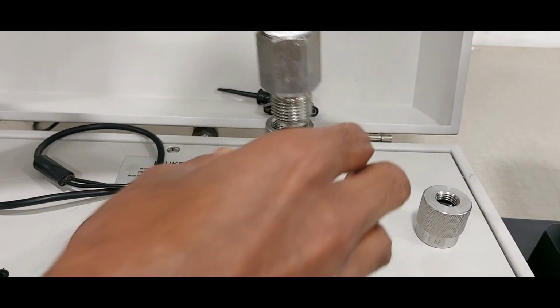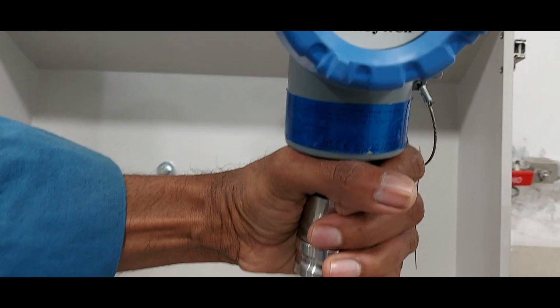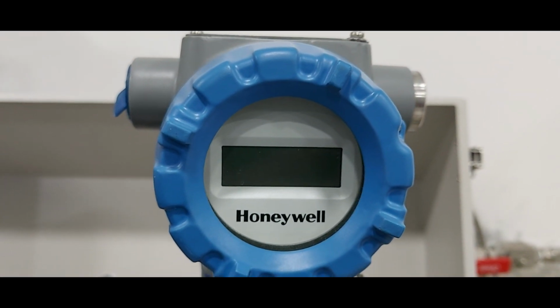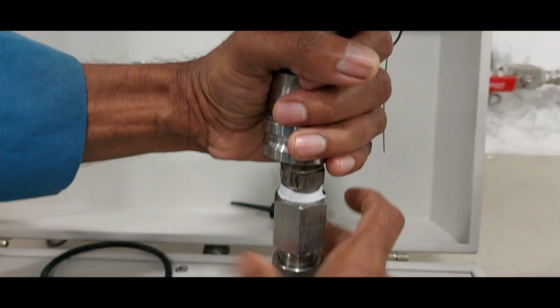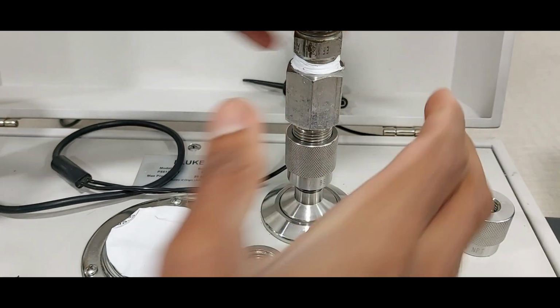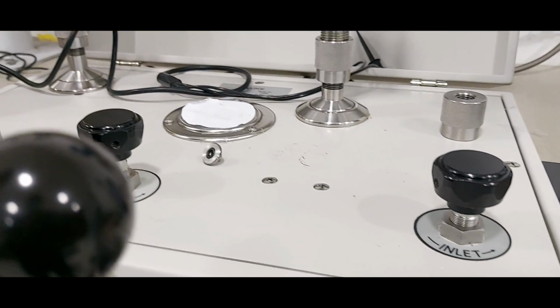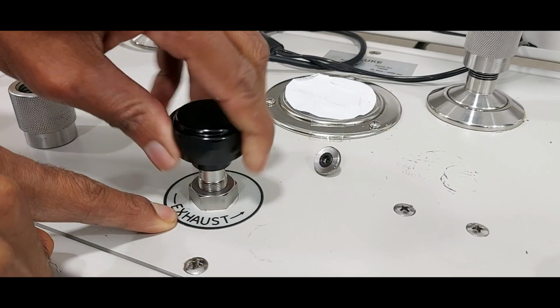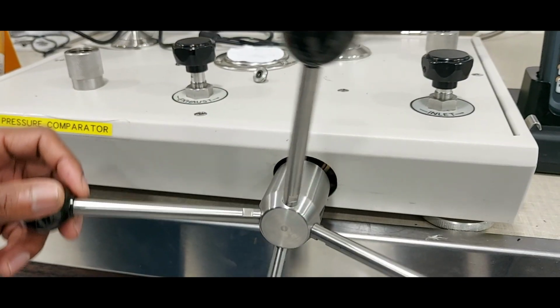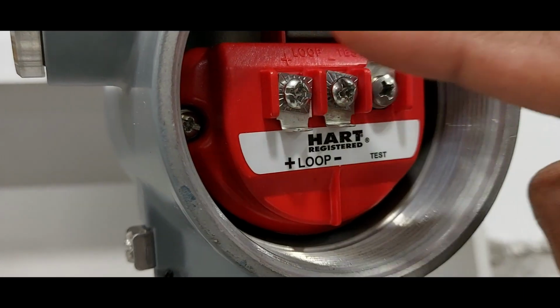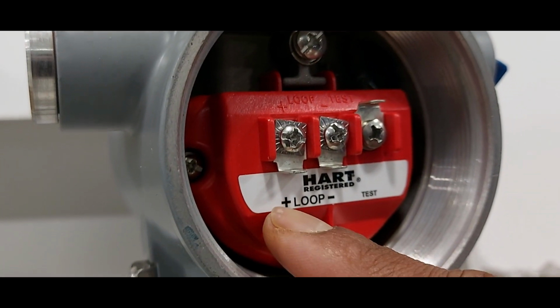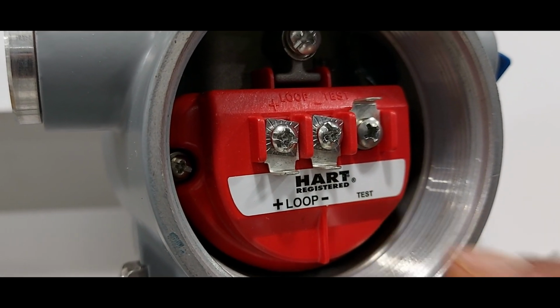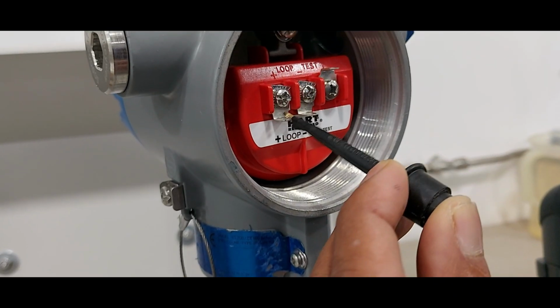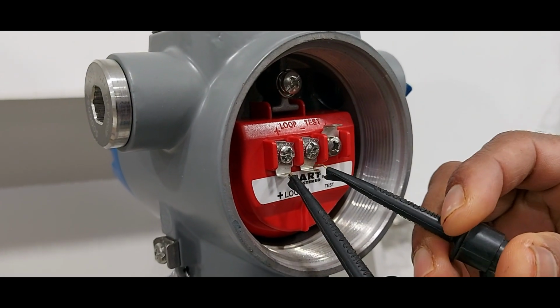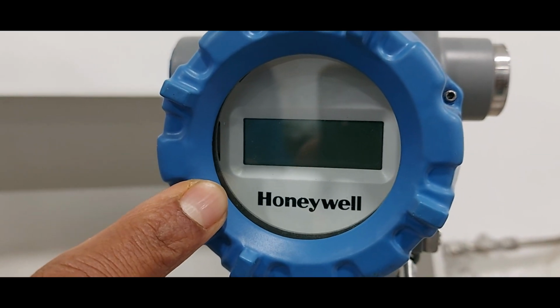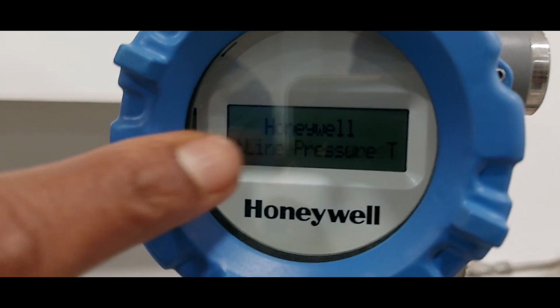We are connecting the transmitter from the output area. Inlet valve, exhaust valve already open, fine adjustment screw pump. Transmitter power supply connection area: positive, negative and test line. Positive connected to positive terminal, negative connected to negative terminal. Now transmitter is power on. SmartLine transmitter.